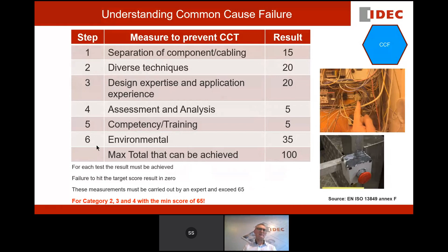So common cause failure is a set of effects that goes into one channel and affects the other channel, but creates a common failure that leads to loss of the safety function. So the initial design going wrong and the specification and getting everything right with the safety integrity, or it could be the way that it's maintained. It could be a loss of wiring in the field. We accidentally use PVC in the field instead of armored cable, and we've got a short circuit in the field.